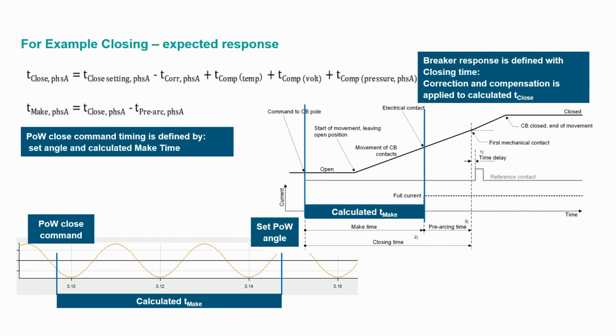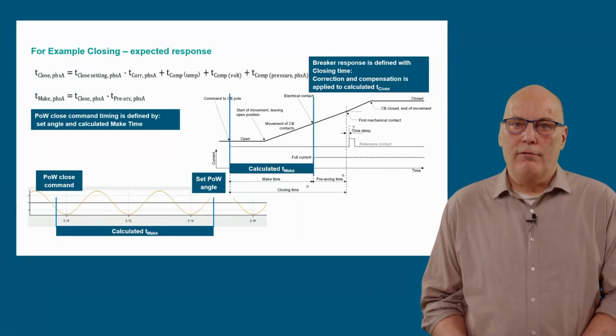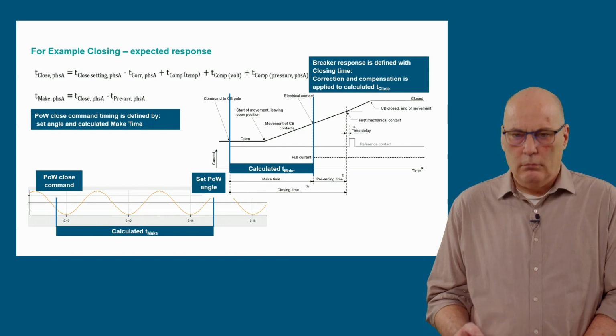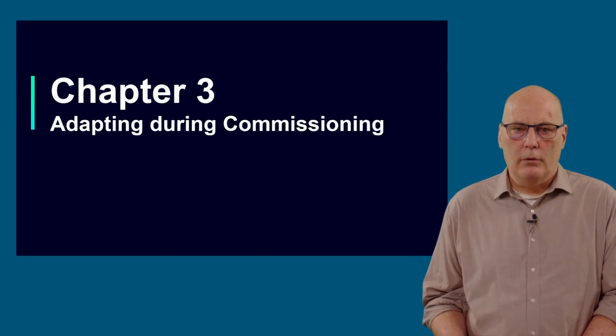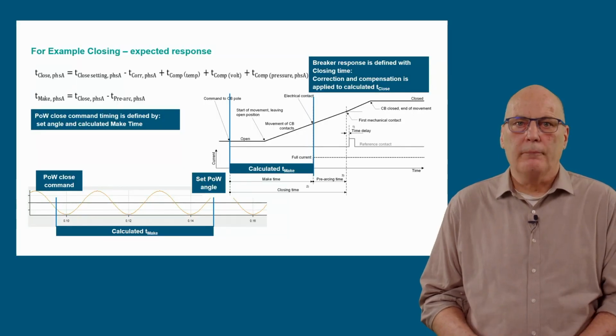Next, the make time is calculated with the set pre-arc time and the above calculated closing time. This is the second equation. It is shown in the right-hand side diagram and will be the time from issue of close command until electrical contact, in other words, current flow. I think I went one slide too far, sorry.